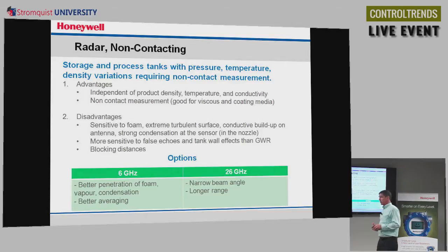It can be a little more sensitive to foam than, say, guided wave radar, and to turbulent conditions, and you can get buildup on the antenna. So if there's a product that you're storing in a tank and there's some vapors that come off of it, if the vapors condense on the antenna, that will cause a problem. That'll block the signal coming out.